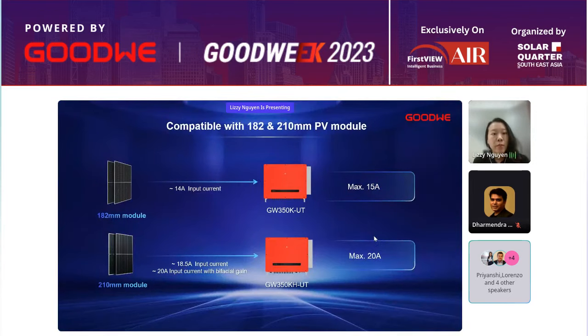Our new products are compatible with 182 and 210 millimeter PV modules. For the 182 millimeter module, the input current of each string can go up to 14 ampere, and for the 210 millimeter module, it can go up to 18.5 ampere per string, or 20 ampere per string if it is bifacial.